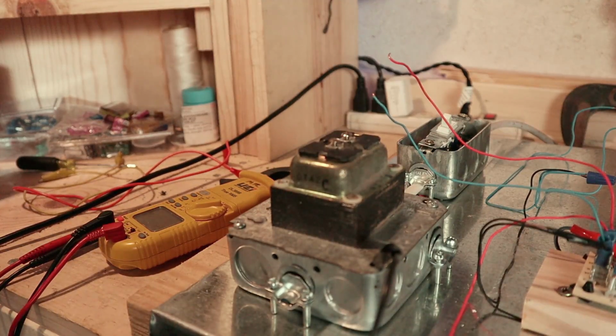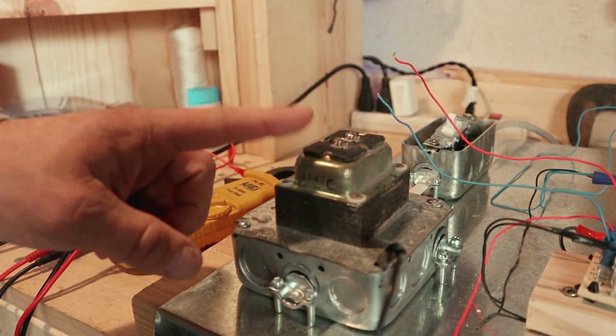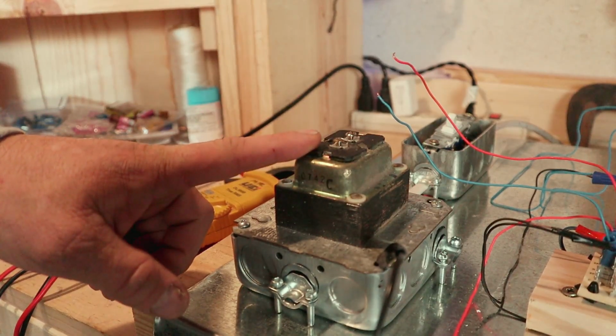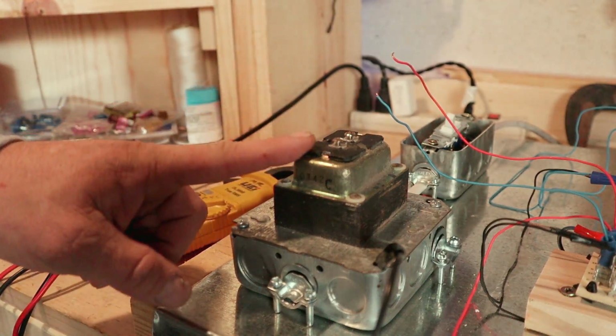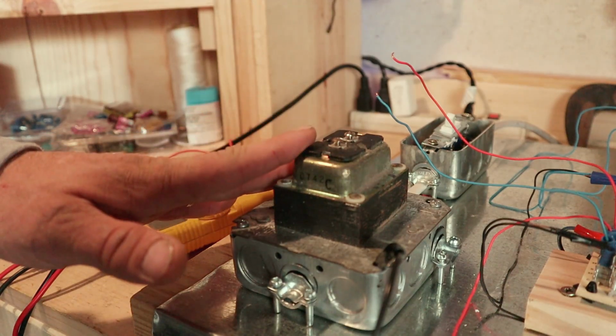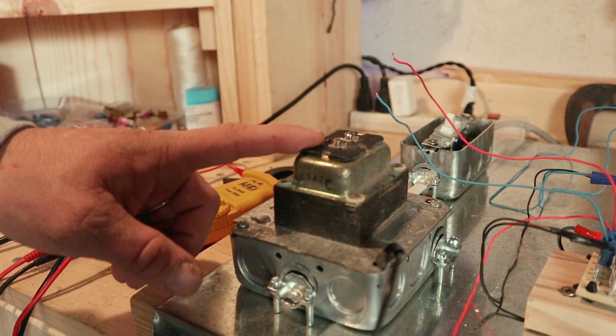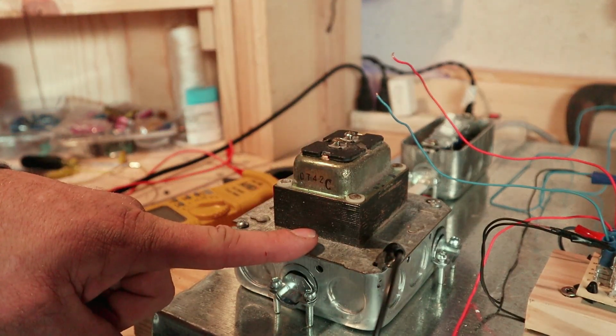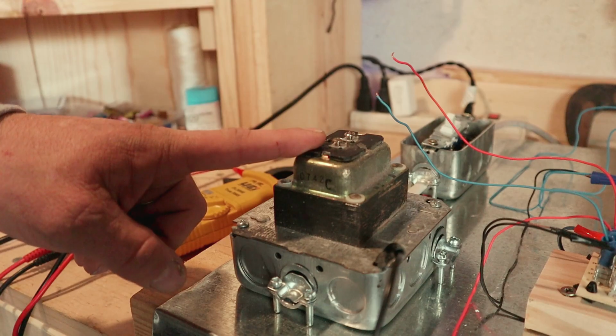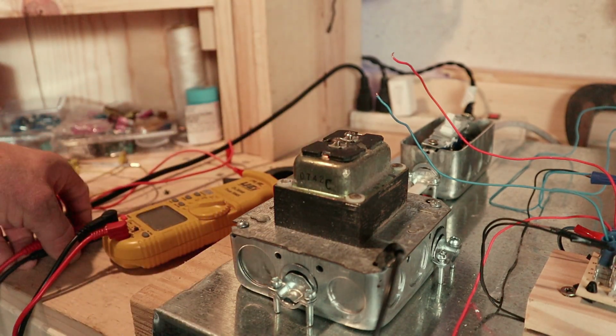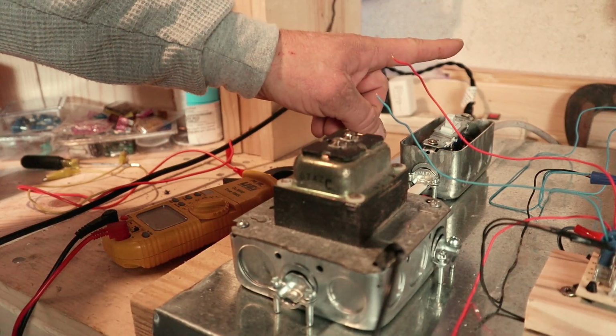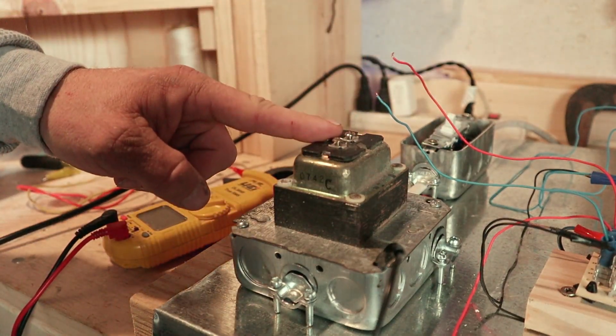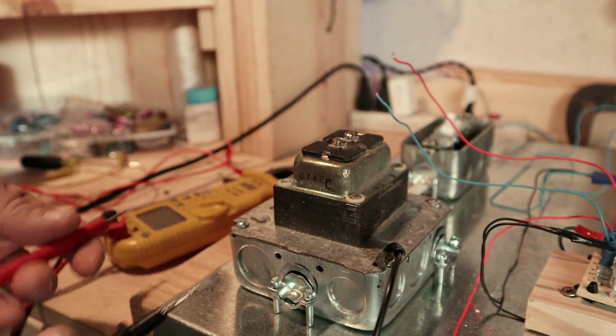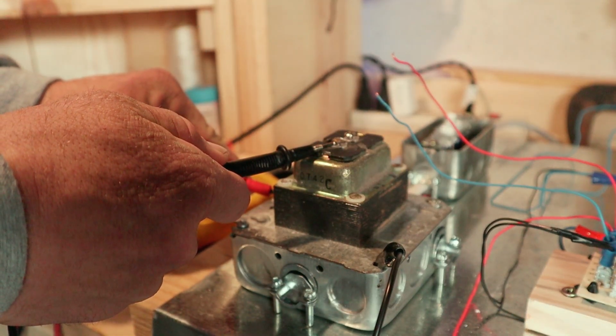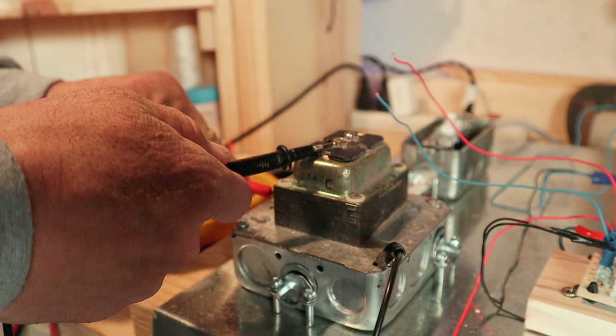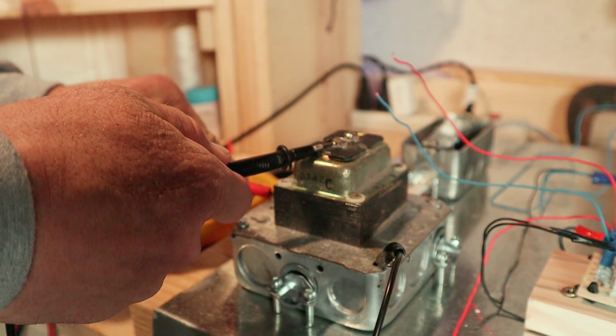Now the first thing I do before I start trying to look for this short is I'm going to come to the transformer and figure out whether or not I have what is called a grounded secondary or a floating secondary. A visual inspection of this isn't always reliable. Sometimes you might actually see a ground wire coming off the transformer and grounding onto a metal surface, but sometimes these transformers are grounded internally. So it's always best to use your multimeter to tell, and to do that, you shut off your power, you disconnect your wires from your transformer, and you do a continuity reading between common and metal chassis. If you're reading continuity there, you have a grounded secondary. If you read nothing, you have what's called a floating circuit.